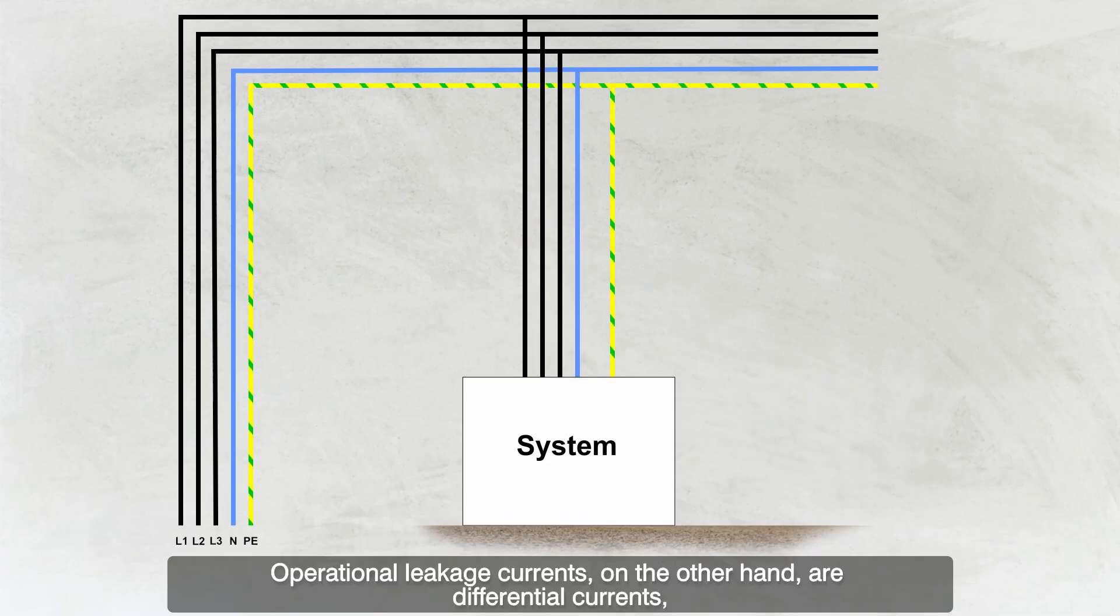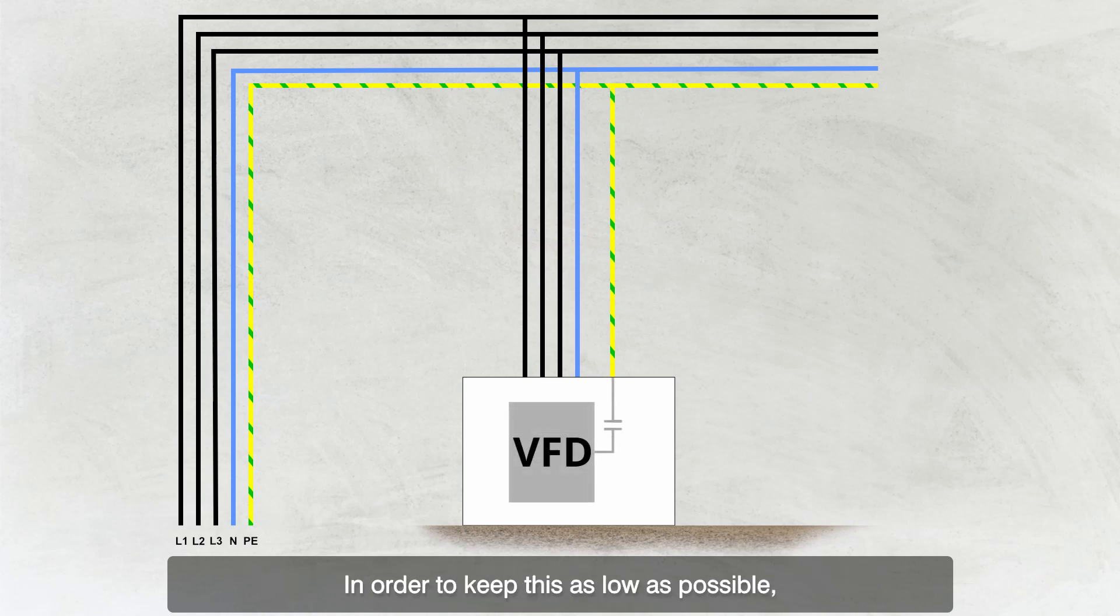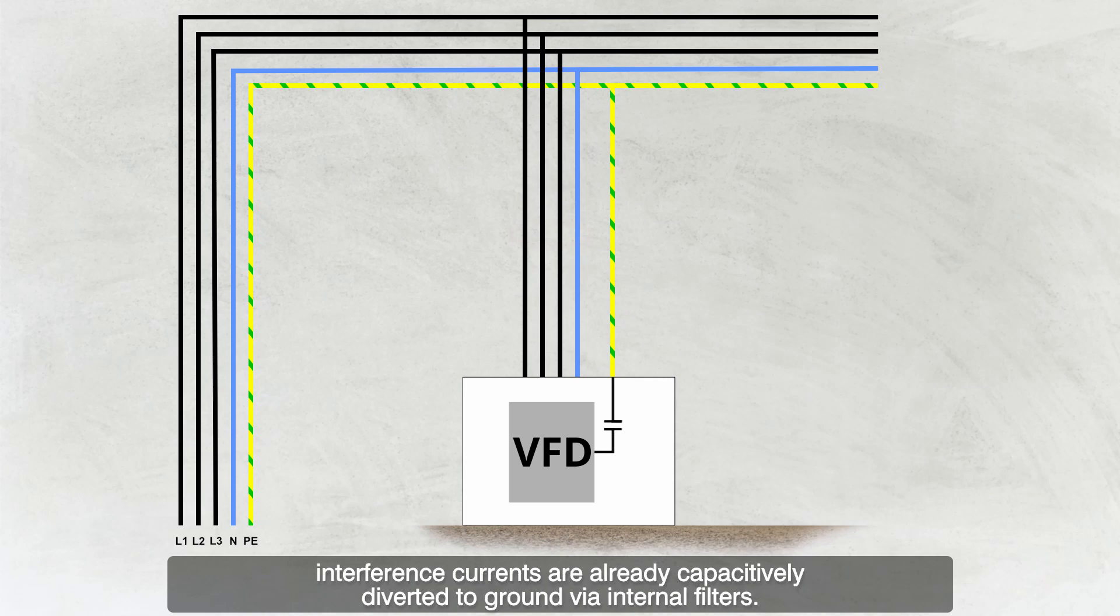Operational leakage currents, on the other hand, are differential currents which flow to earth during normal operation without a fault being present. In order to keep this as low as possible, interference currents are already capacitively diverted to ground via internal filters.